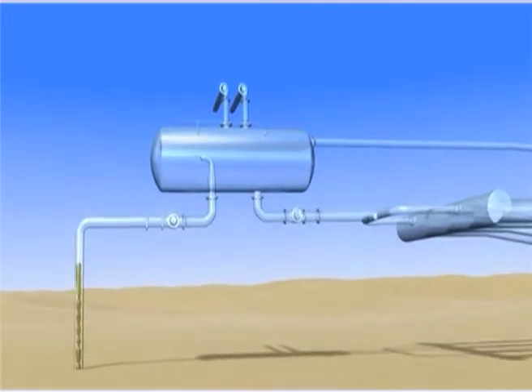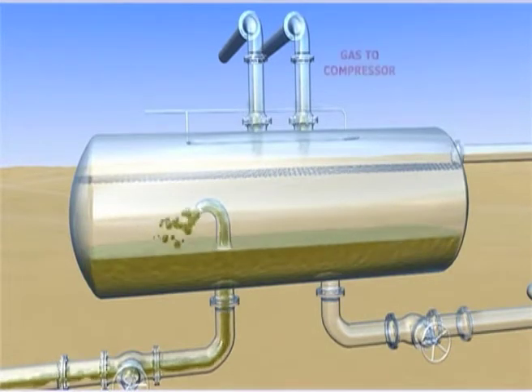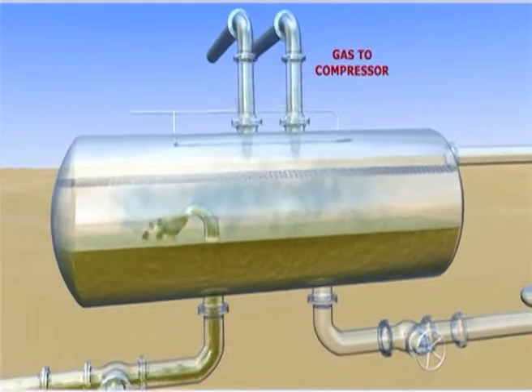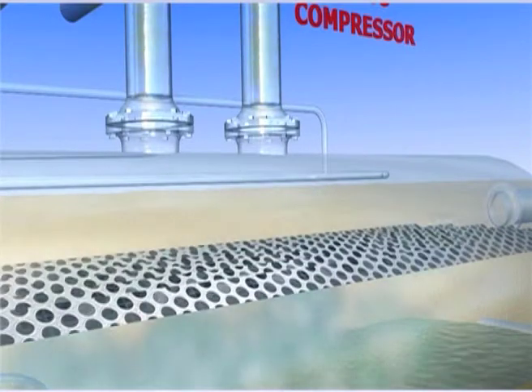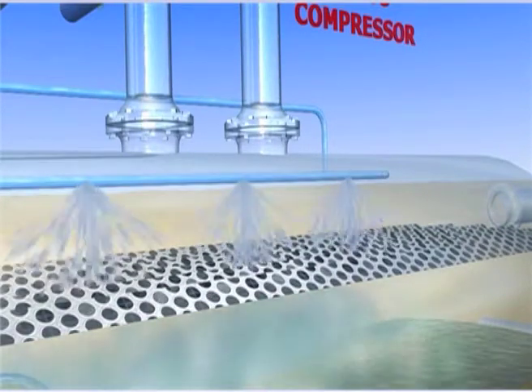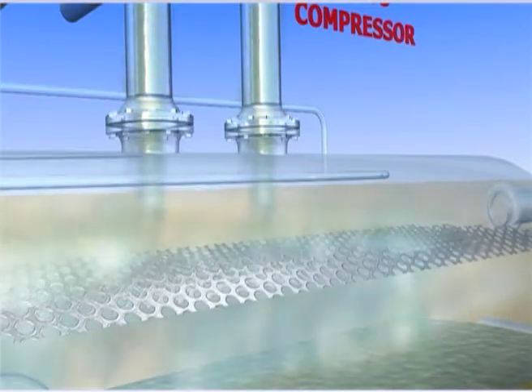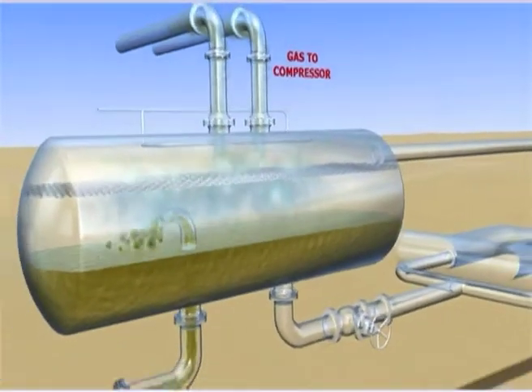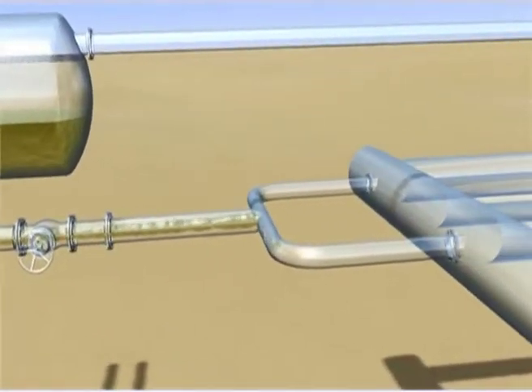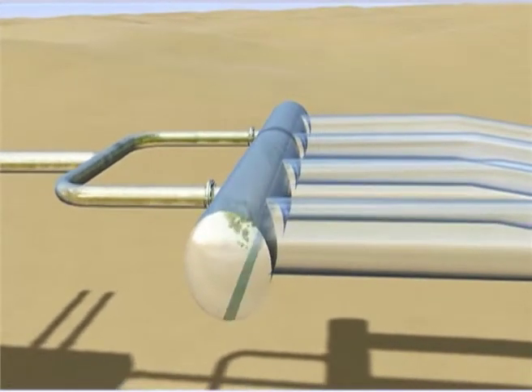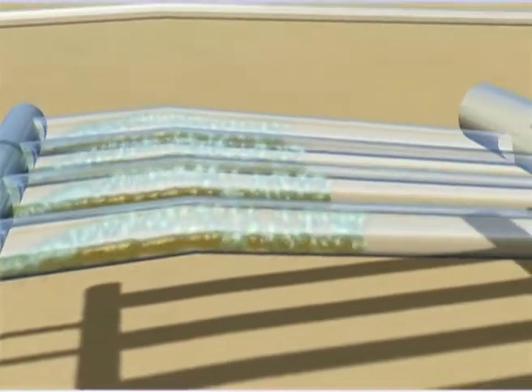The two-phase flow of gas and liquids in the pipelines operates as slug flow regime. Due to gravity, liquids will tend to settle on the bottom while the gases occupy the top section of the pipeline. The slug catcher is a vessel with sufficient buffer volume to store the largest slugs expected from the upstream system. It is located at the entrance of the processing facility. The buffered liquids can be drained to the processing equipment at a much slower rate to prevent overloading the system. As slugs are a periodical phenomenon, the slug catcher should be emptied before the next slug arrives.